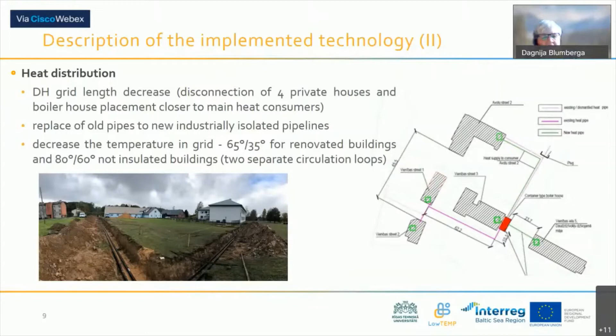Not only the temperature level will be 65/35 with a return temperature of 35 - is it possible? Yes, it is. Monitoring showed that it was possible, instead of previous 100 to 70, and then 80 to 60. The question was only about buildings which were not insulated, and what to do and how to supply heat to that non-insulated dwelling building.